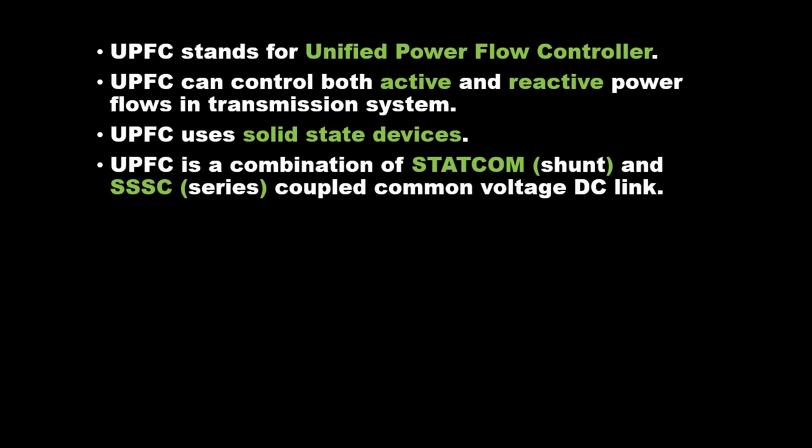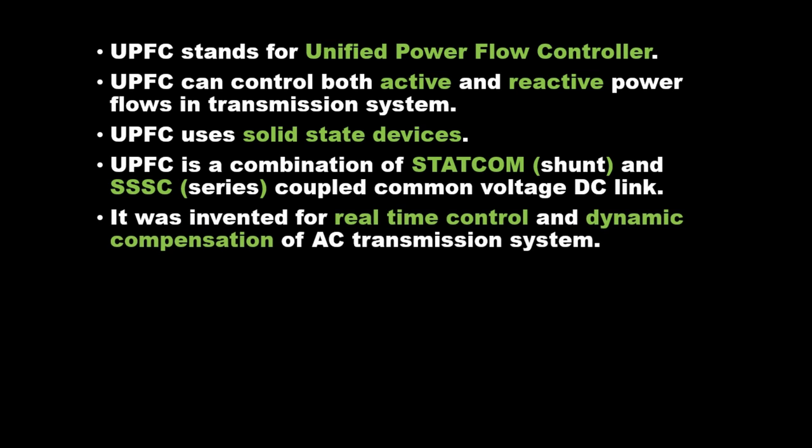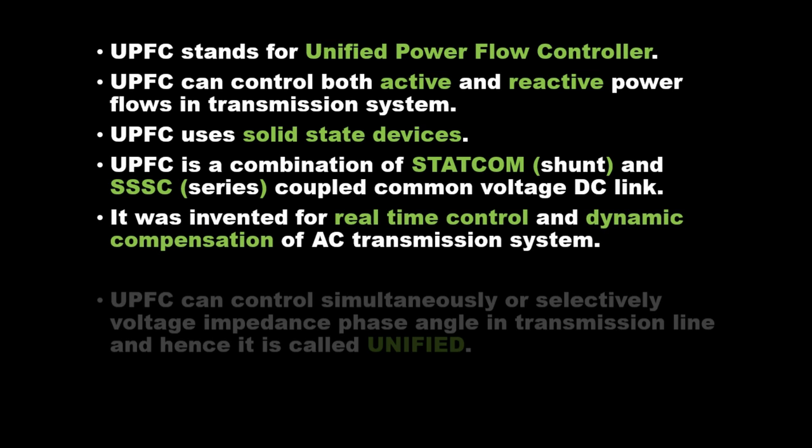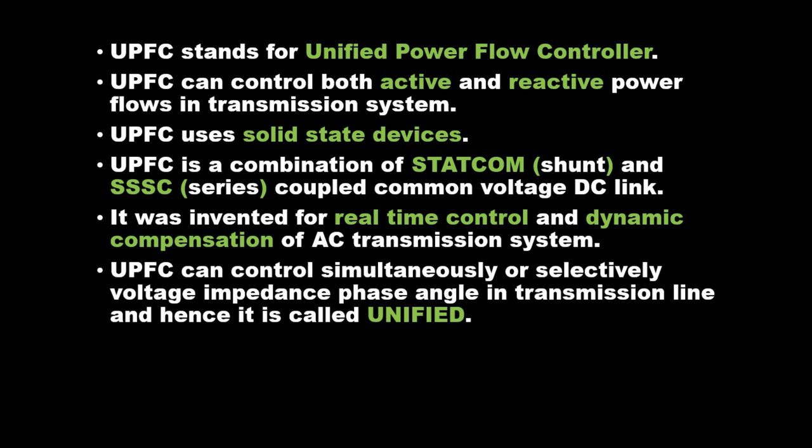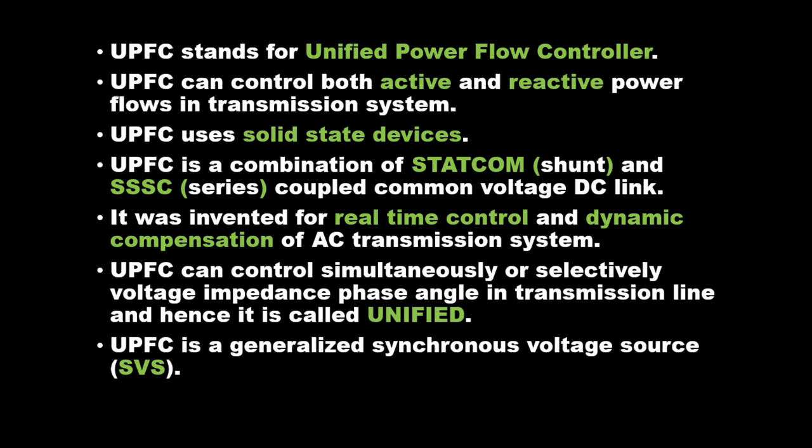UPFC is a combination of STATCOM shunt and SSSC series, coupled by a common voltage DC link. It was invented for real-time control and dynamic compensation of AC transmission systems. UPFC can control simultaneously or selectively voltage, impedance, and phase angle in transmission line, and hence it is called unified.